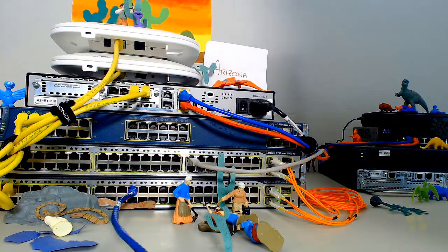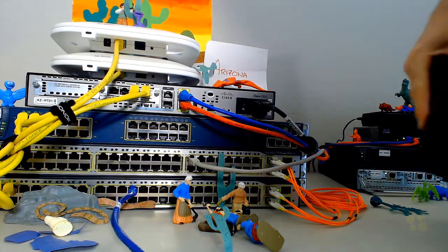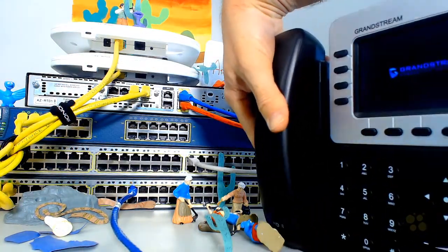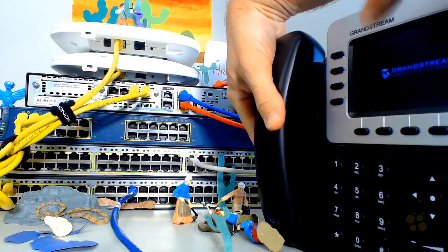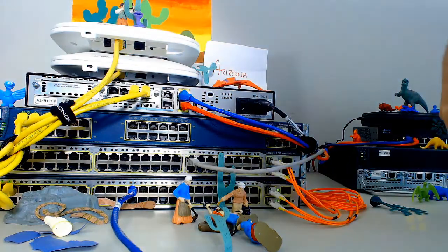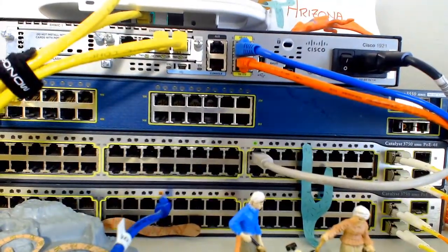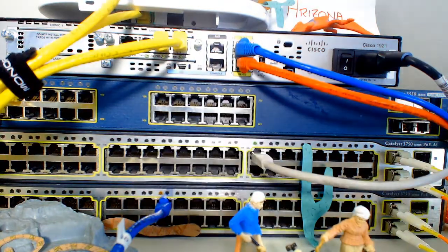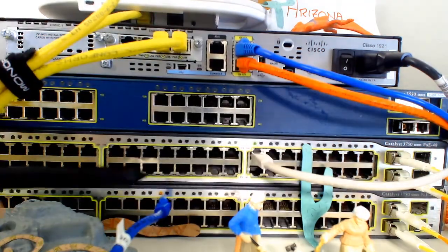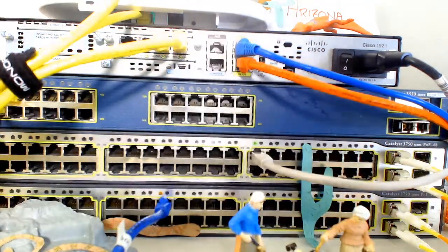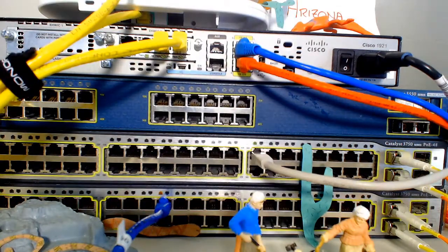Now you can see behind the scenes, it's a little dim. Let me zoom in a little bit. Well, I'll show right on the screen. You can see the phone has begun to power on and go through its boot cycle. But right here on the switch itself, you can see that the port has gone active, sort of. The port is amber because of spanning tree. It takes 30 seconds to go live and active, but it's still sending power down the port so the device that's attached to it can start booting.